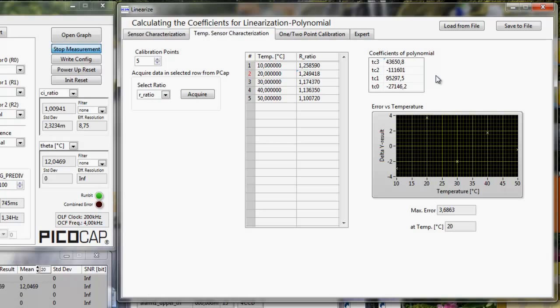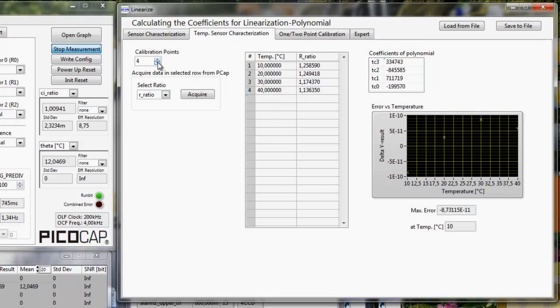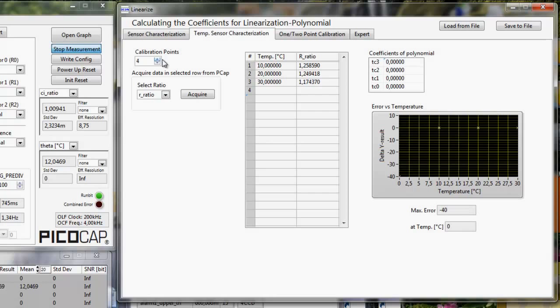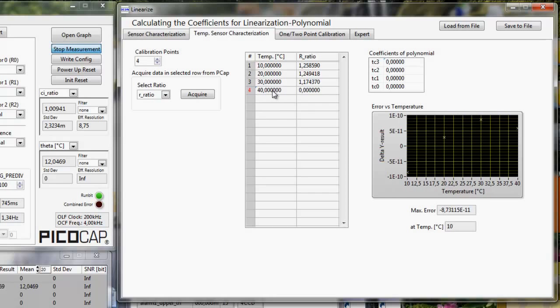One note here, at the current state of the software as of April 2013, we have here a little limitation still, which is you need at least 4 calibration points. So if you go further down, you see with 3 calibration points the coefficients come to 0. This is due to the mathematical calculations in the background and will be fixed soon.